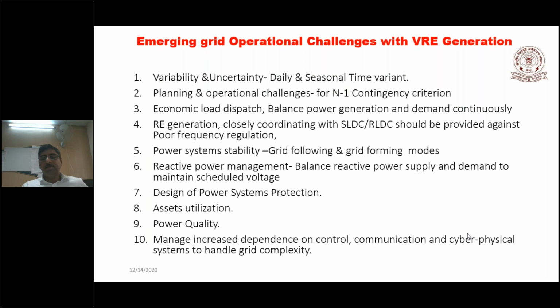Let me explain stability in terms of voltage control. Typically in the grid, voltage is controlled by the synchronous machines, which maintain 1 per unit voltage irrespective of loading, since they have an exciter provided. Suppose I have a two area system, area A and area B—at all times the voltage is controlled by the machine. Suppose area 2 has a PV based system. The PV system will work in current control mode and will follow the voltage of area 1, since area 1 has the synchronous machine. So the whole system voltage is controlled by the synchronous machine, and the PV system just follows it—there's nothing unusual there.